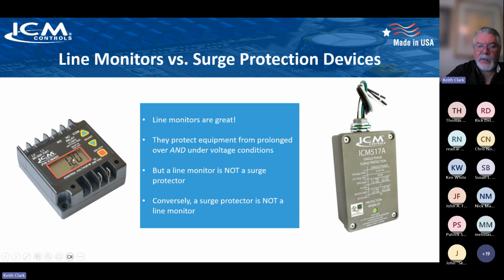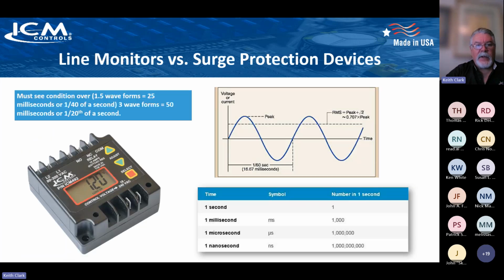So line monitors are great. These over here, they protect equipment from prolonged overvoltage and undervoltage conditions. But a line monitor is not a surge protector. Conversely, a surge protector is not a line monitor. So these are two different animals. They're two different events, but they really go hand in hand. With the line monitors, you're able to monitor incoming voltage continuously. And what a line voltage monitor needs to see is a condition over at least 1.5 waveforms. Now this is adjustable. You can have the interrogation period.